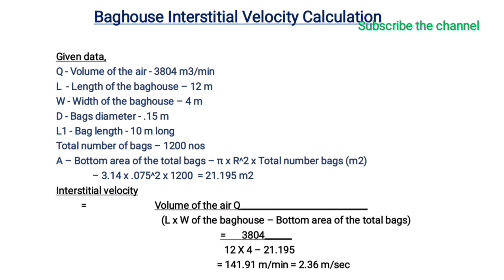Now we understand how to calculate the interstitial velocity in the bag house. Given data: Q — volume of air 3,804 cubic meters per minute; L — length of the bag house 12 meters; W — width of the bag house 4 meters; D — bag diameter 0.15 meters; one bag length 10 meters; total number of bags 1,200. First, we calculate the bottom area of the total bags: A equals pi multiplied by R squared multiplied by the total number of bags. Based on this data and formula, the bottom area of the total bags is 21.195 square meters.